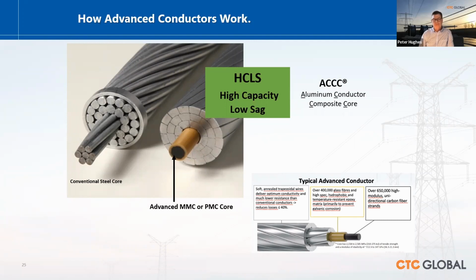In terms of performance, we must consider the conductor on the left as a system. The steel core and alloy conductor strands all act together to provide the conductor with its inherent strength. For the conductor on the right, that's not the case. It's only the composite core that finally delivers the mechanical properties above a given temperature. This permits the use of pure aluminium as the conductor material, because it doesn't require mechanical properties, and pure aluminium compared to an alloy has about 10% less inherent resistance than its alloy equivalent.